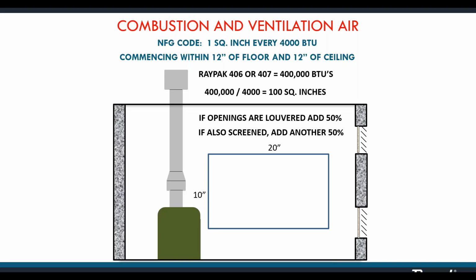All right? 2 things to bear in mind here. First of all, in this example, we have 1 heater in the room. What if you have 2 heaters? What if you got 1 for the pool, 1 for the spa? What if you got 2 heaters and a hot water heater or a boiler that's also in the room, or 2 boilers? You have to account for all of the BTUs in the room. So you would add the rating plate input, BTU input for all of those devices, add those all together, and make sure that the holes are sized accordingly.